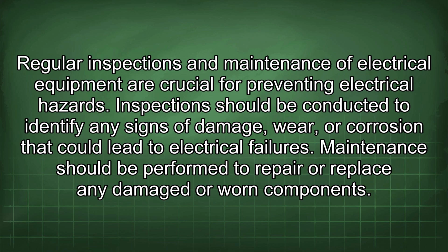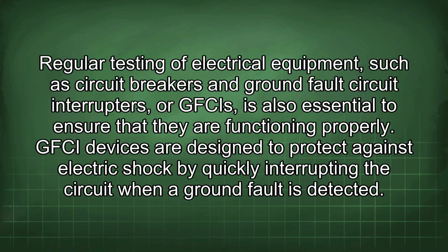Regular inspections and maintenance of electrical equipment are crucial for preventing electrical hazards. Inspections should be conducted to identify any signs of damage, wear, or corrosion that could lead to electrical failures. Maintenance should be performed to repair or replace any damaged or worn components. Regular testing of electrical equipment, such as circuit breakers and ground fault circuit interrupters, or GFCIs, is also essential to ensure that they are functioning properly. GFCI devices are designed to protect against electric shock by quickly interrupting the circuit when a ground fault is detected.